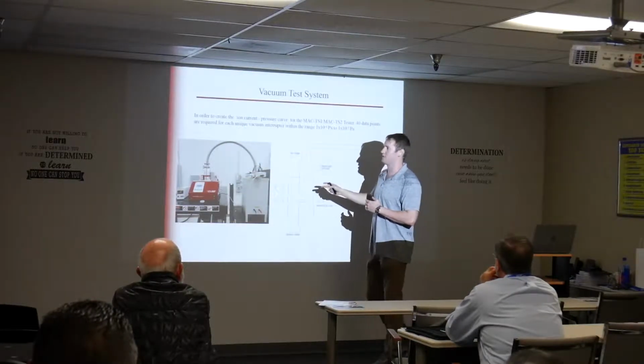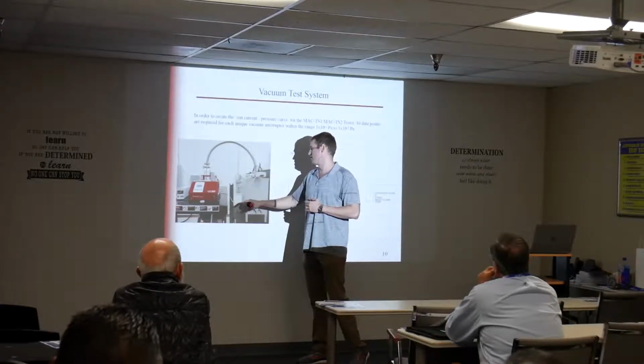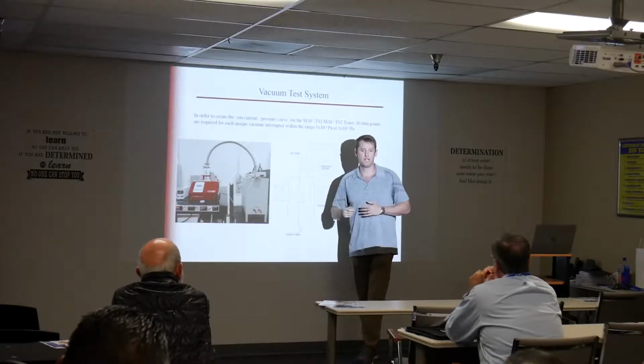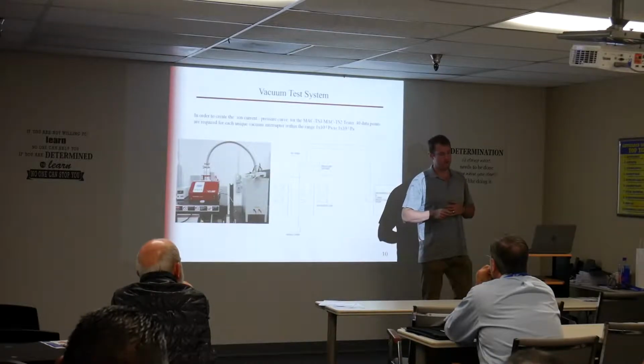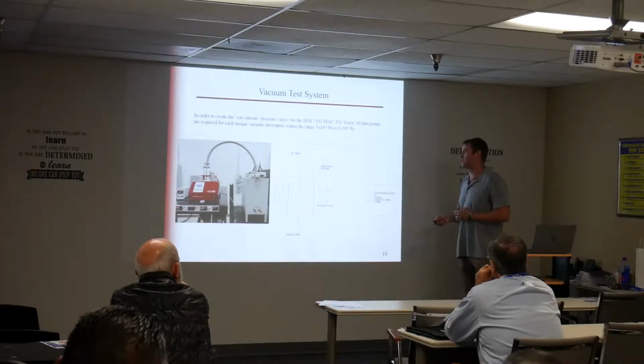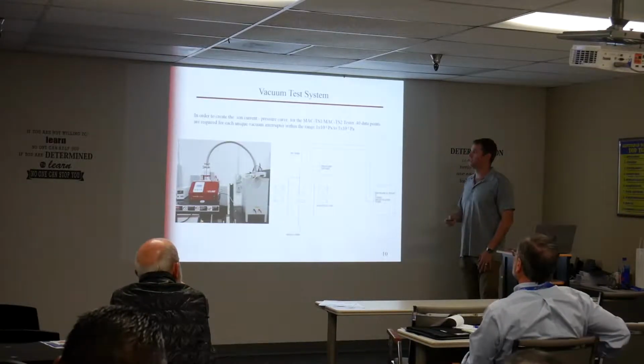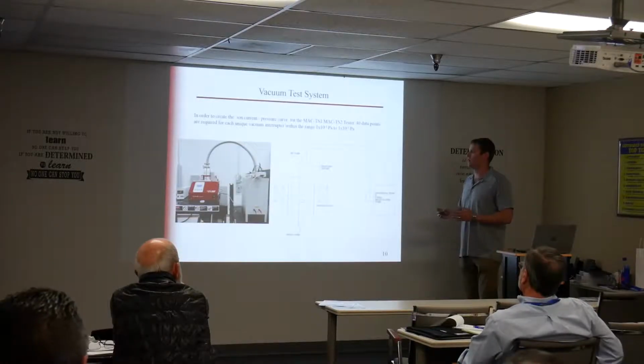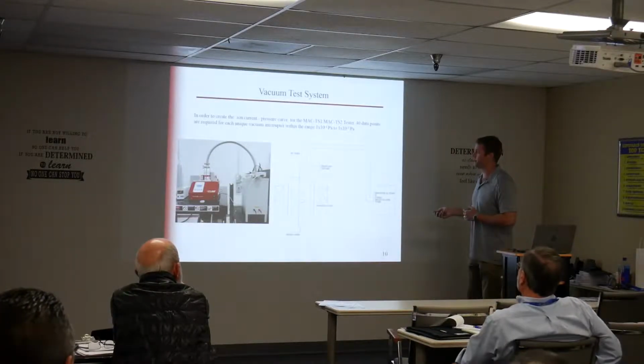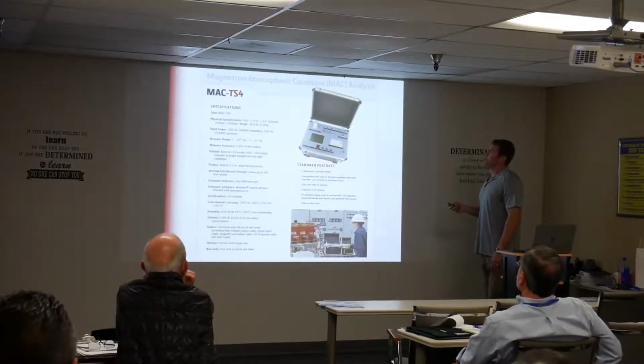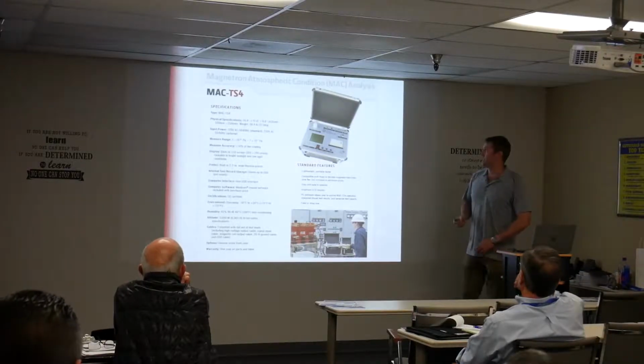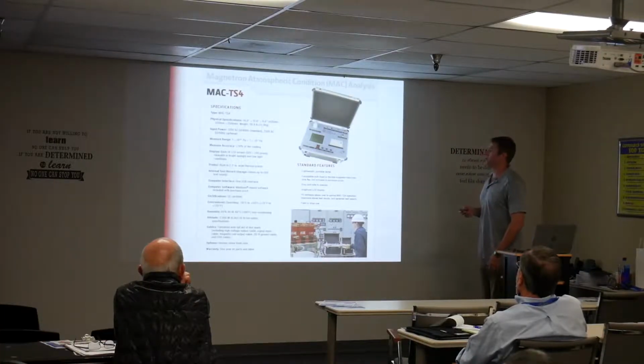So I know for this size interrupter, at this pressure, I get this current. I pump it up and down, 40 data points down, 40 data points up, and I use that to program these algorithms that go in the test set. So that's just how we convert from current to pressure. So this is our 4th generation test set, MAC-TS4.